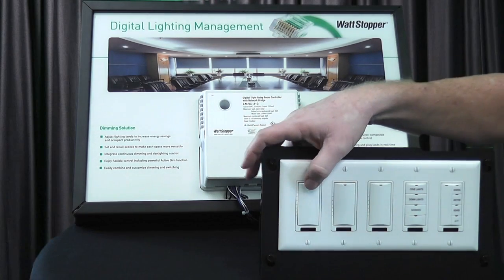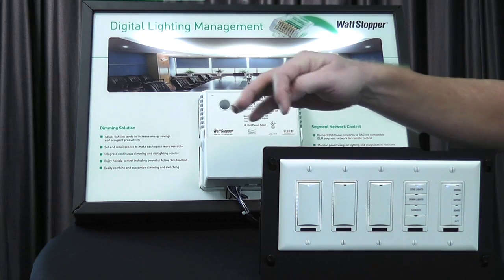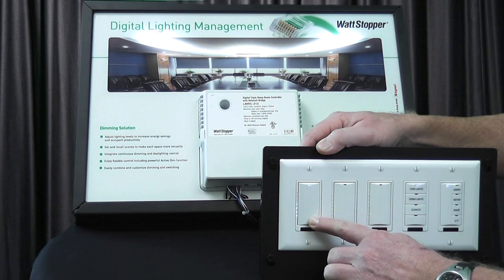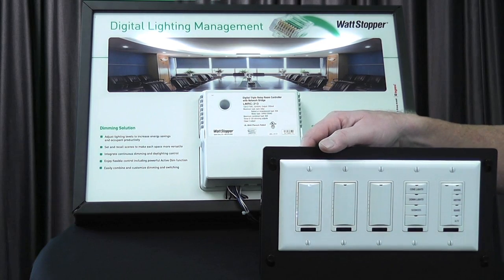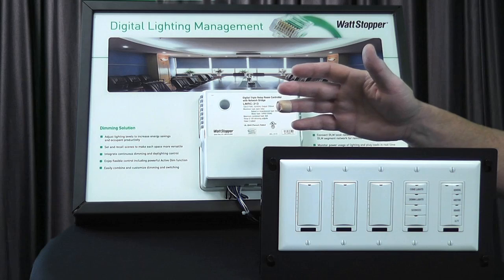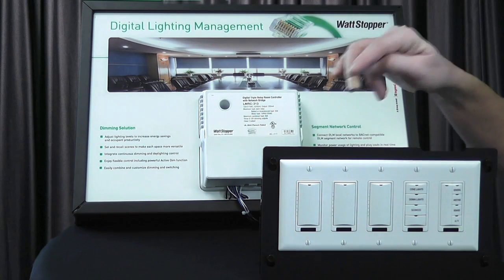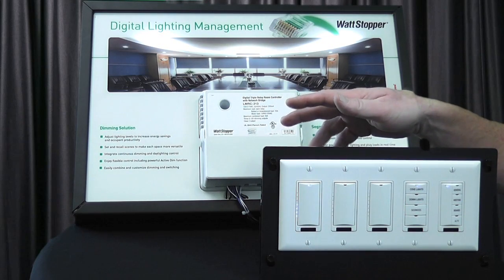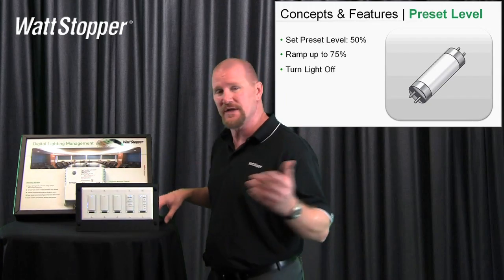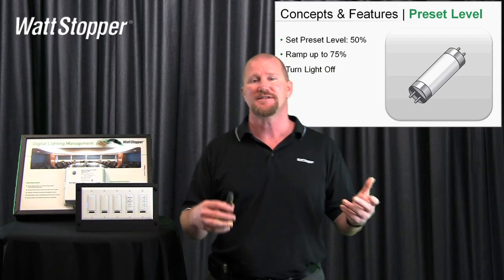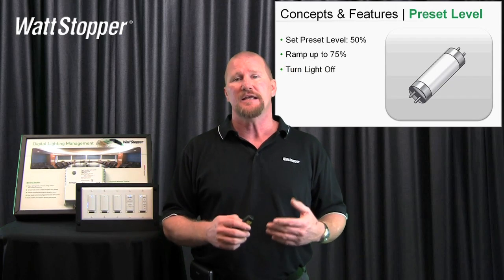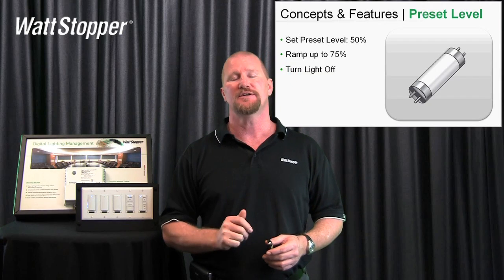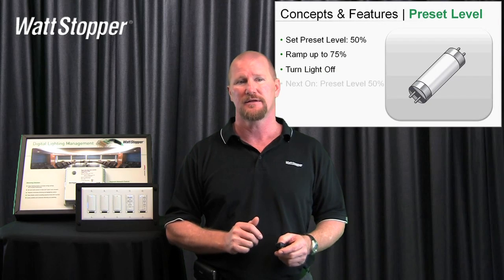Over here on the keypad, I'm going to turn on the first dimmer. I'll dim down to 50%. When I turn it off, the preset level by default is 50% — that's the last level the dimmer was at. If I tap it, it comes on to 50%. The feature we're going to give you with digital lighting management is the ability to set a persistent preset level: I'll set a preset level of 50%, and no matter where I leave the load, every time I turn it back on, it's going to come on to 50%.